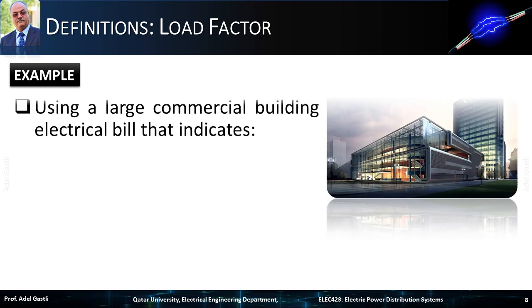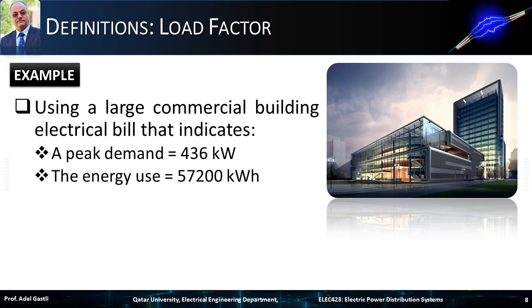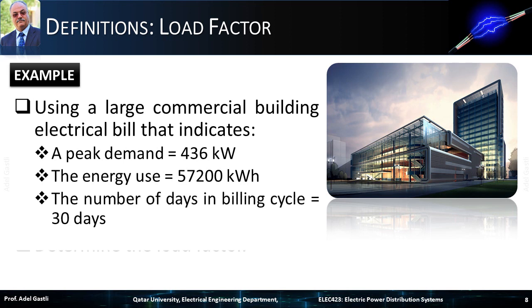Let's see an example of load factor calculation. We consider a large commercial building with a monthly electrical bill showing the following information: the peak demand during the billing period equals 436 kilowatts, the total energy used during the billing period equals 57,200 kilowatt hours, and the number of days in the billing cycle equals 30 days. We want to calculate the load factor for this commercial building during the billing month.